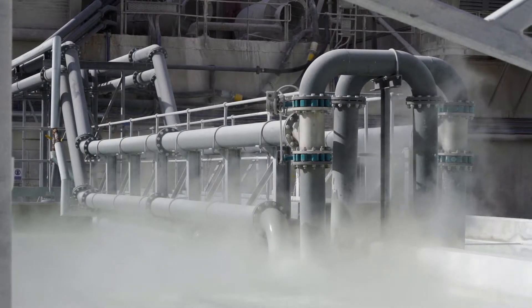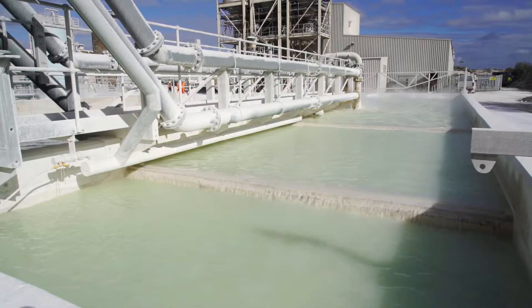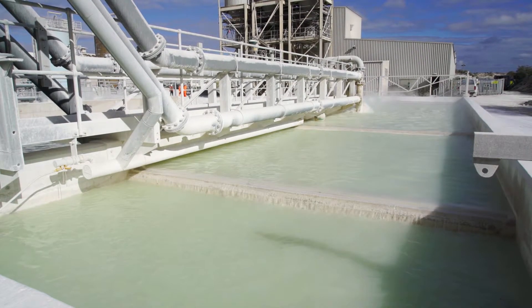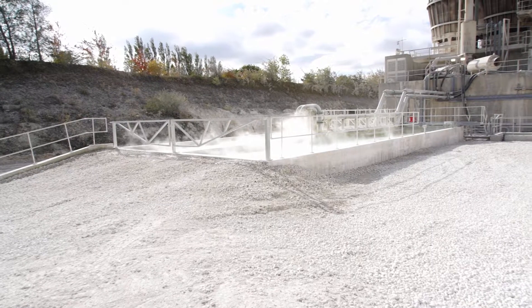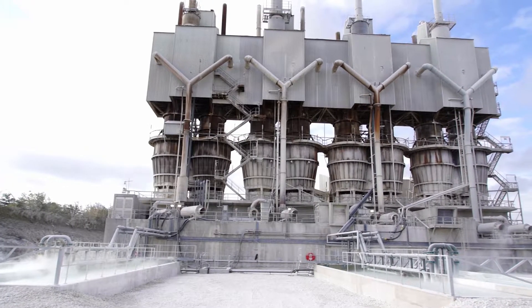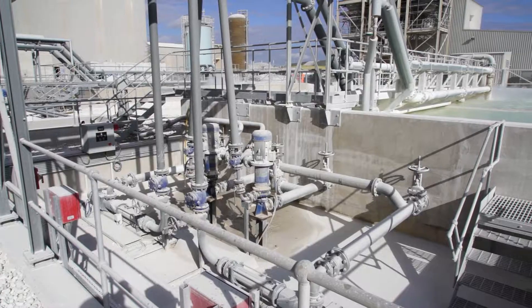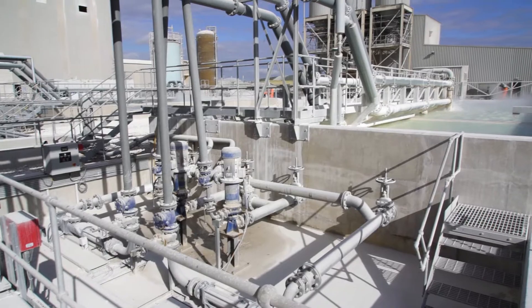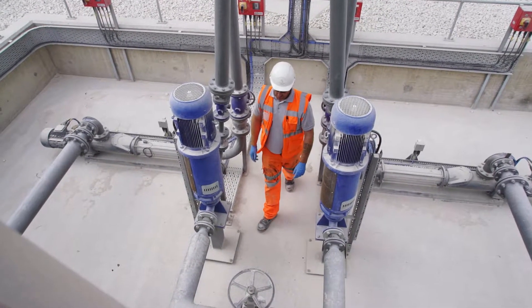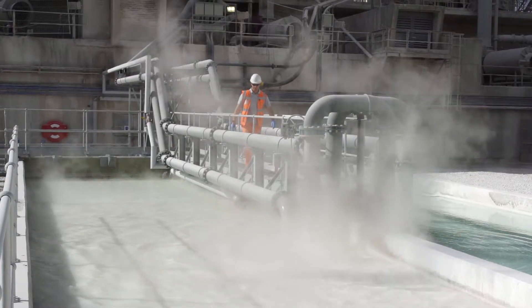Initially we looked at the tanks themselves and moved towards a concrete tank. Part of the design involved relocation — although built on the existing site, we moved the tanks around so we had better crane access and better maintenance access. The centrifugal pump and the cavity pumps are now separate from the tanks, so they avoid being in contact with any water. Operators now have safe access along a catwalk to reach all the valves they need to alter.